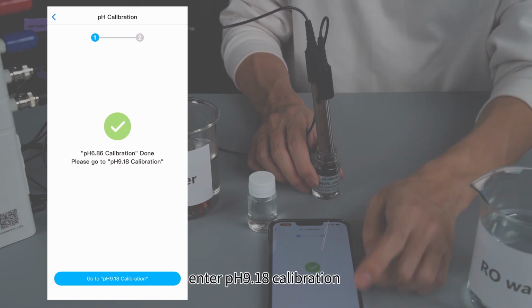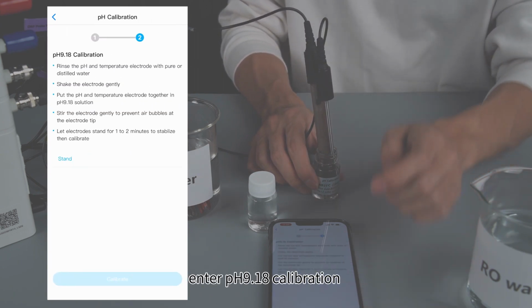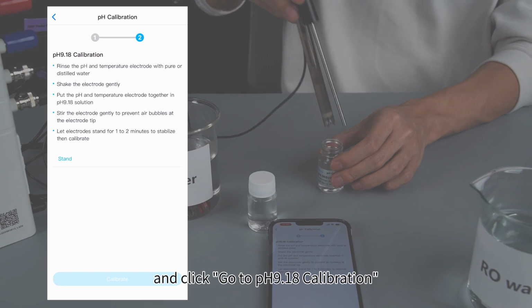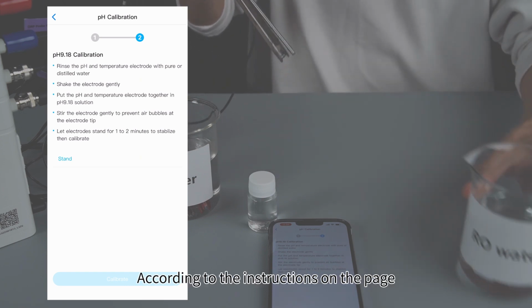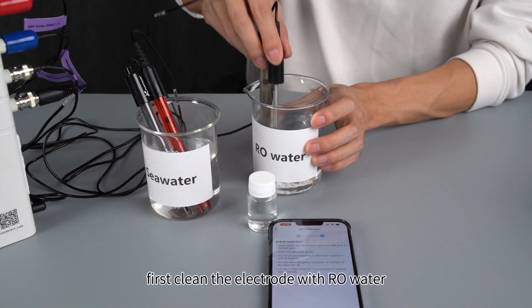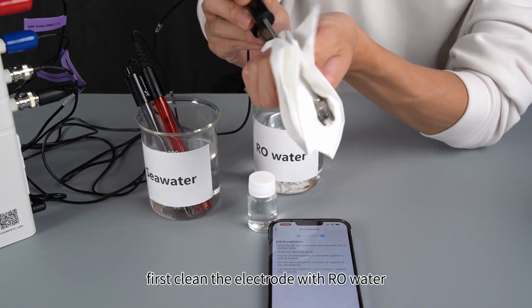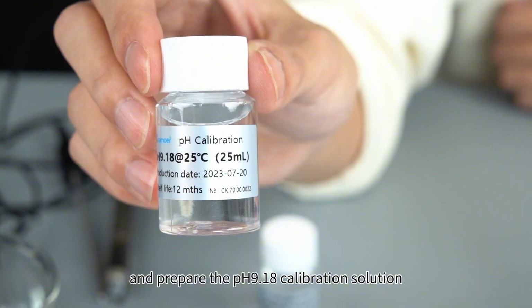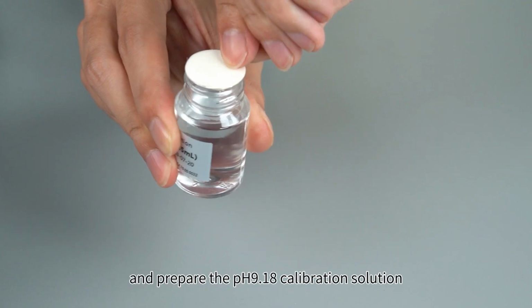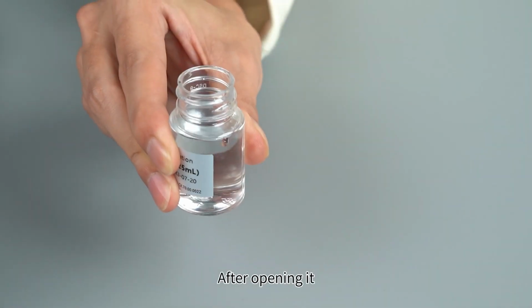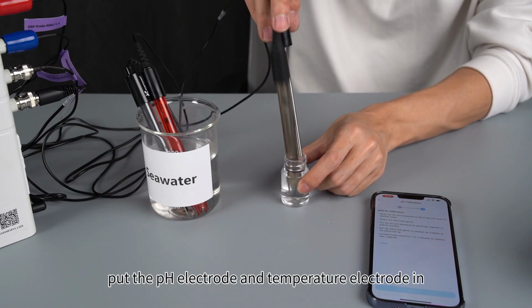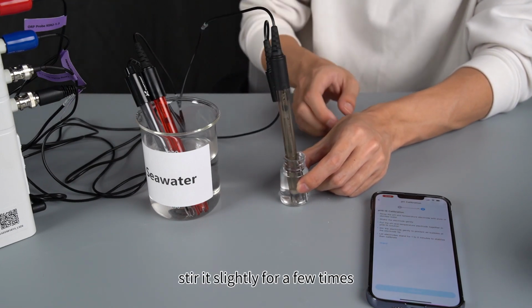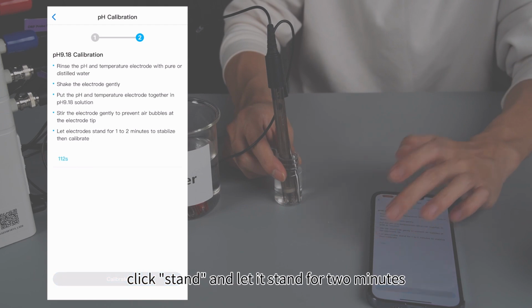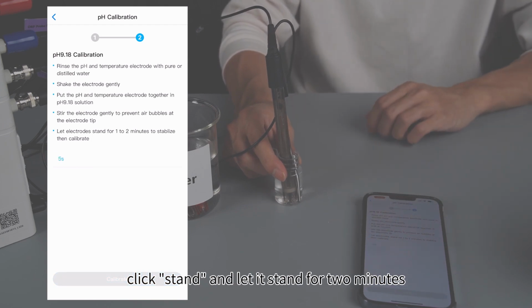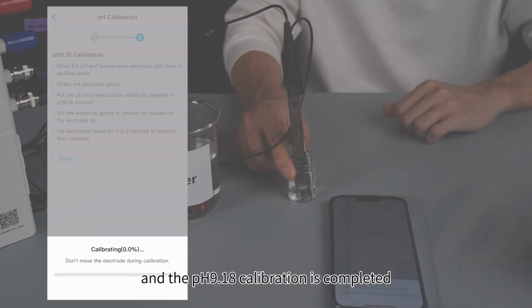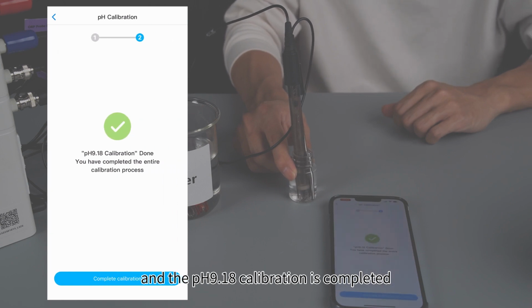Next, enter pH 9.18 calibration, and click Go to pH 9.18 calibration. According to the instructions on the page, first clean the electrode with RO water, dry it with paper, and prepare the pH 9.18 calibration solution. After opening it, put the pH electrode and temperature electrode in. Stir it slightly a few times. Click Stand, and let it stand for 2 minutes. Click Calibrate, and the pH 9.18 calibration is completed.